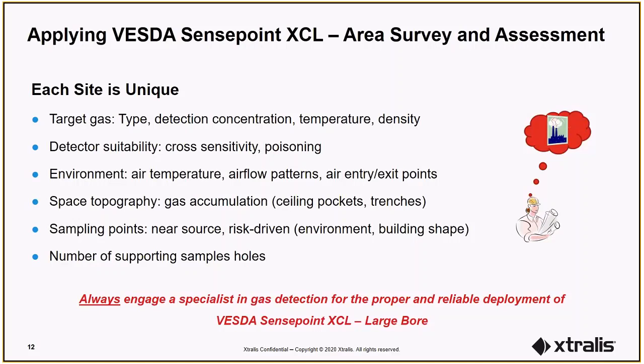When applying VESDA Sensepoint XCL, you must understand that each area has its own unique set of conditions that can impact gas detection. For example, what and where are the gas hazards? What are the physical properties of the gas? What are the environmental conditions within the space? For example, how will airflow and ventilation impact gas movement? Is there a likelihood for gas accumulation where detection might be required? Should you design for localized detection or follow performance-based design, taking into consideration the built environment? Will actual operations in the area change throughout the year, and how can this impact the system? Always engage a specialist in gas detection for the proper and reliable deployment of VESDA Sensepoint XCL large bore product.